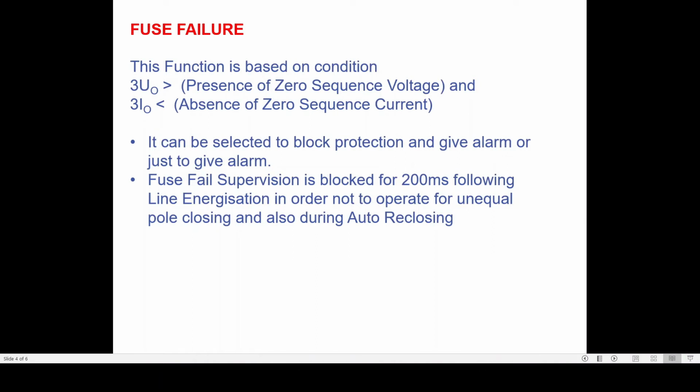But in case of three phase voltage failure, three phase fuse failure, the relay now doesn't see any zero sequence voltage. So now the relay gets confused and it will detect it as a fault and it might issue a trip command. But again, this is not a fault condition. So there must be a second logic also inside the relay. That second logic is called the delta voltage method.